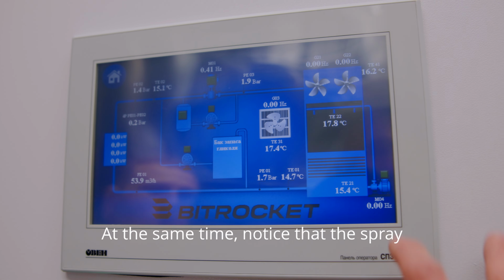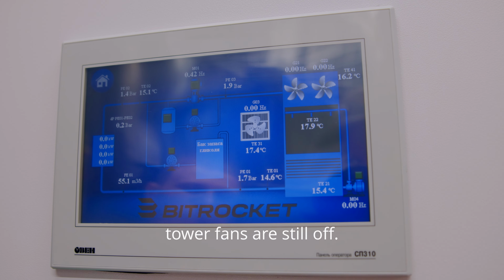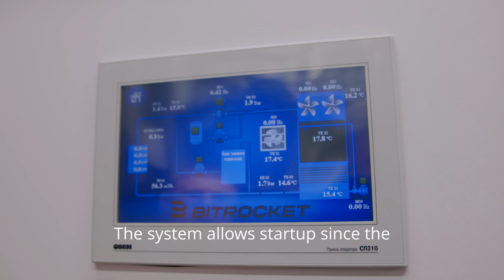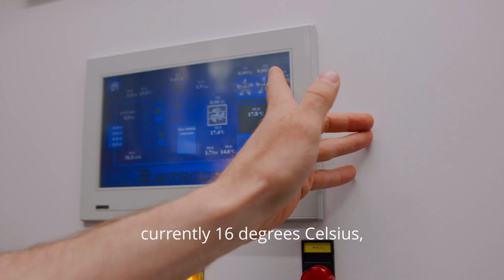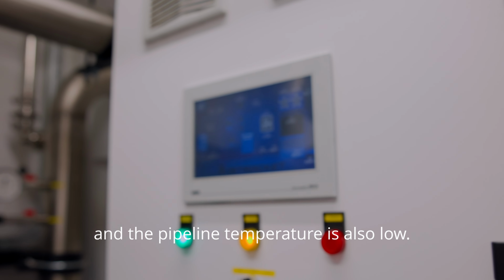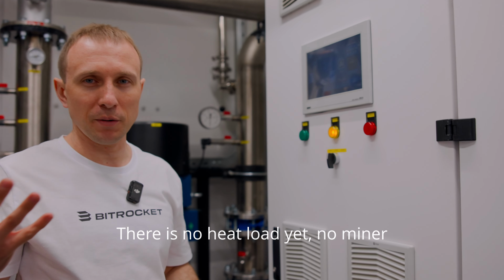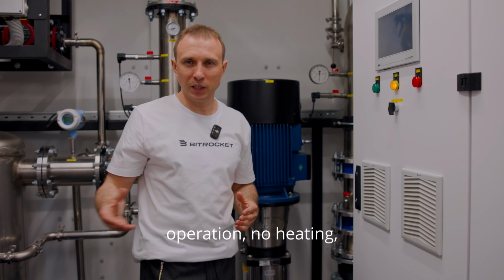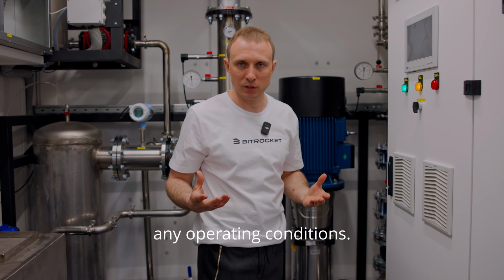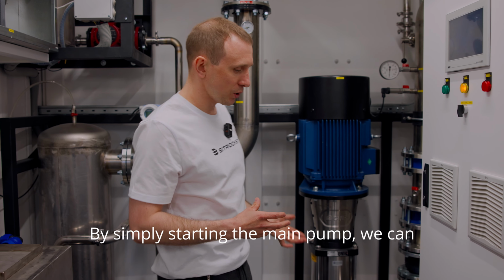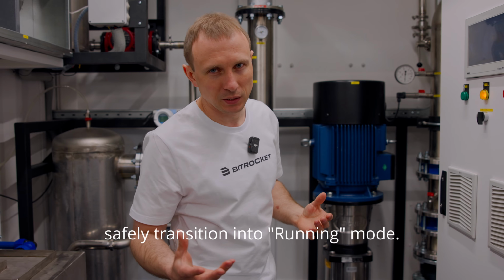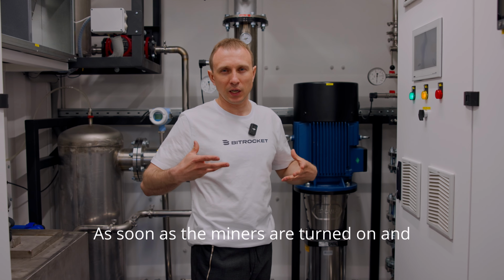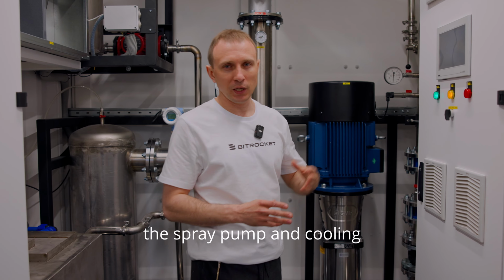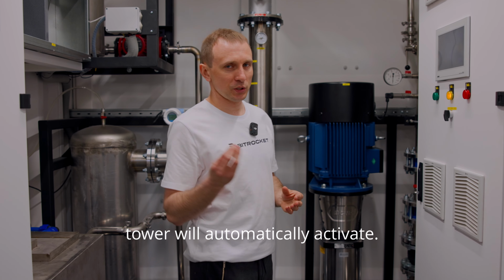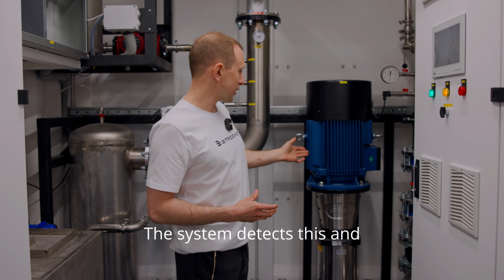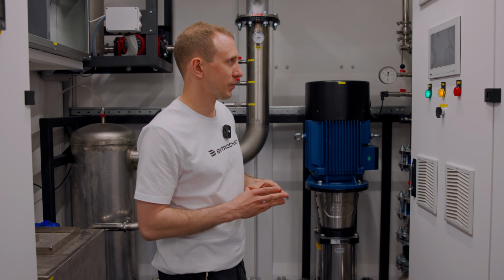At the same time, notice that the spray pump and cooling tower fans are still off. Why? The system allows startup, since the ambient temperature is currently 16 degrees Celsius, and the pipeline temperature is also low. There is no heat load yet, no miner operation, no heating. So we're not violating any operating conditions. By simply starting the main pump, we can safely transition into running mode. As soon as the miners are turned on and begin generating heat, the spray pump and cooling tower will automatically activate. The system detects this and turns them on independently.